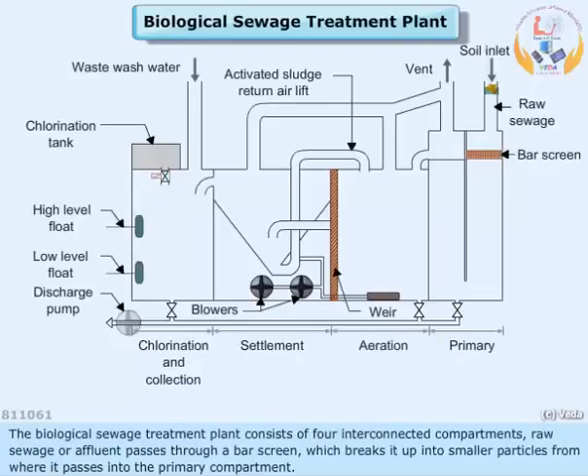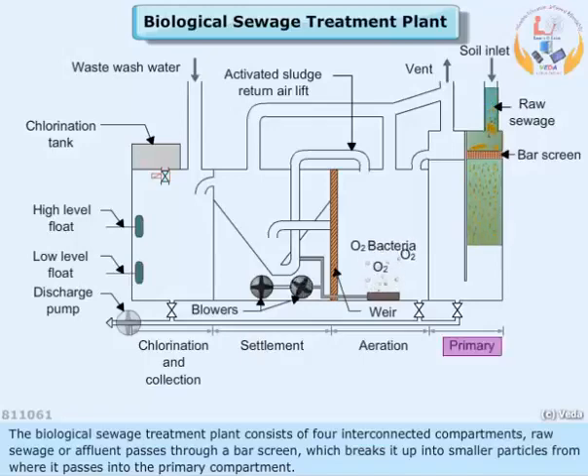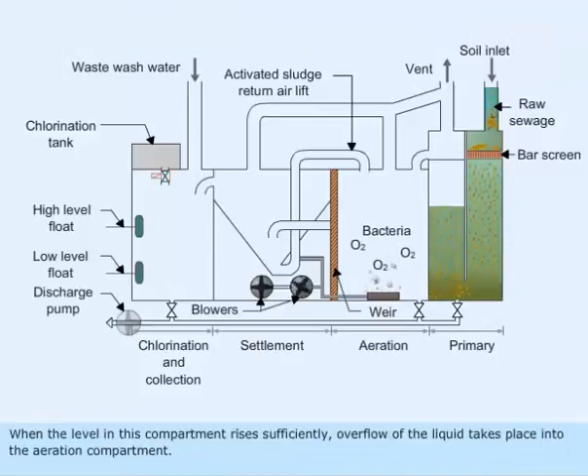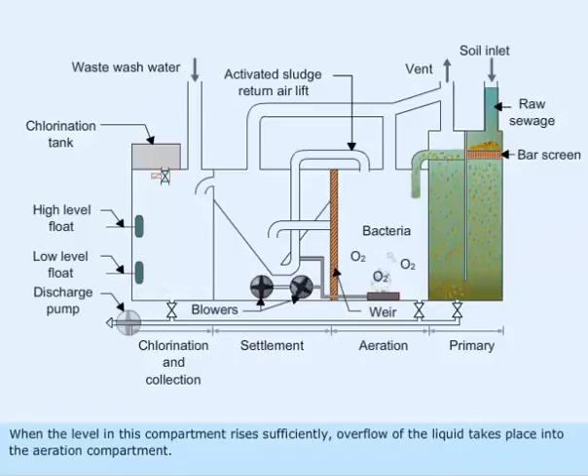The biological sewage treatment plant consists of four interconnected compartments. Raw sewage or effluent passes through a bar screen which breaks it up into smaller particles, from where it passes into the primary compartment. When the level in this compartment rises sufficiently, overflow of the liquid takes place into the aeration compartment.